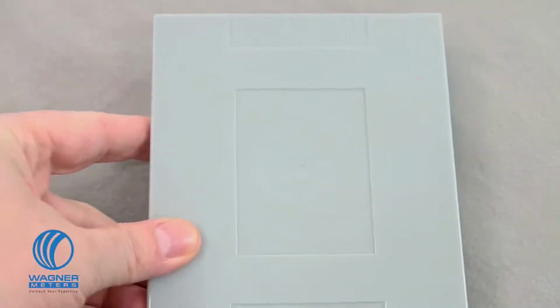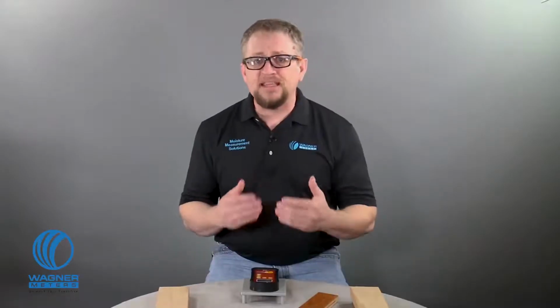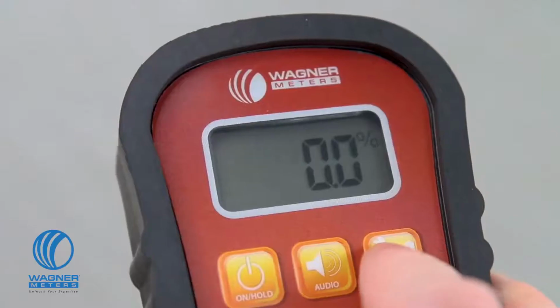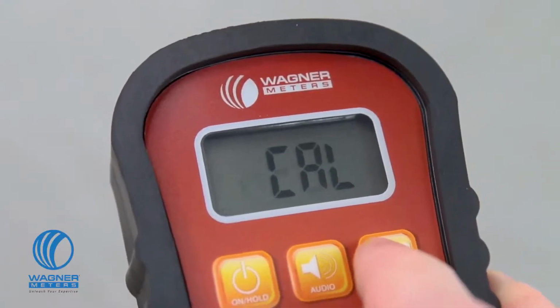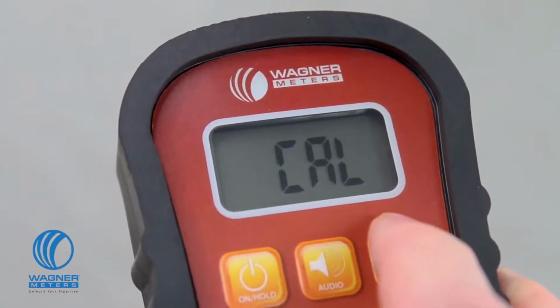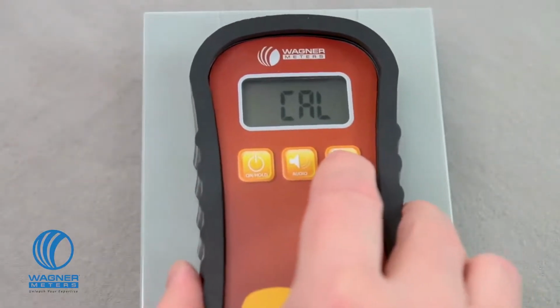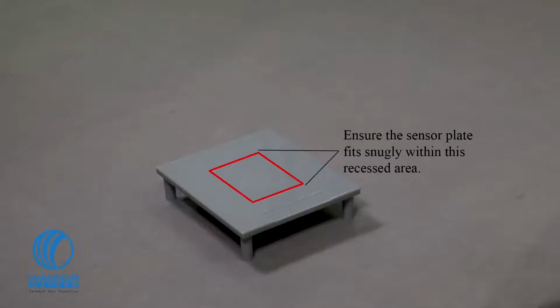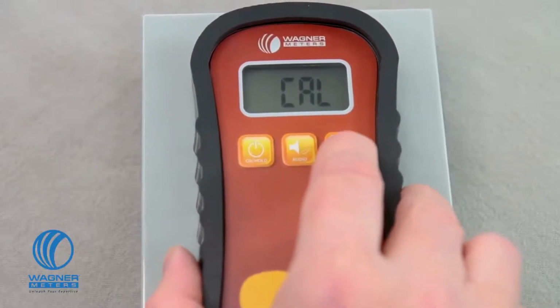Place the calibration reference on its legs on a flat surface. Turn the meter on, and then use the species material button to put your meter in cal mode. Place the meter on the calibrator, correctly seating the meter sensor pad firmly on the recessed area. This is important because if you place the sensor pad anywhere else, it will cause an inaccurate calibration. Move it back and forth, side to side, to make sure the pad is firmly seated.